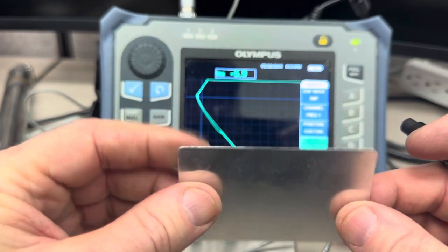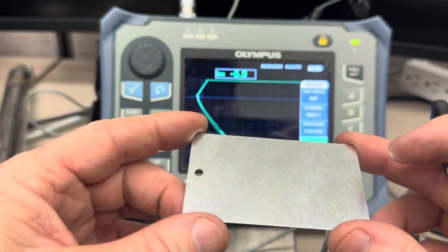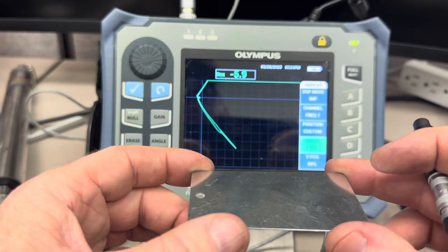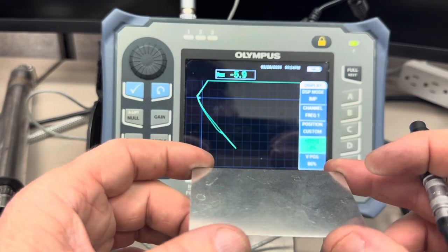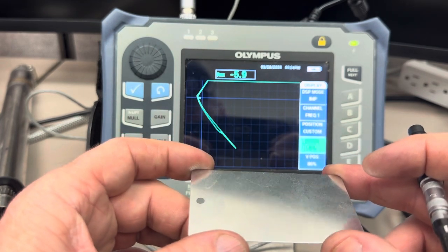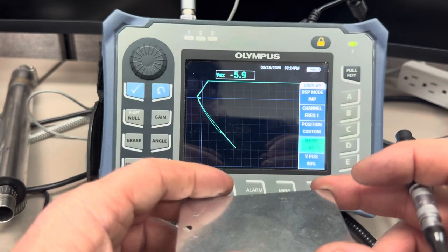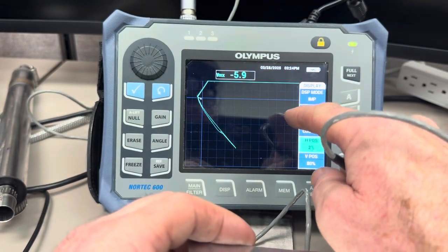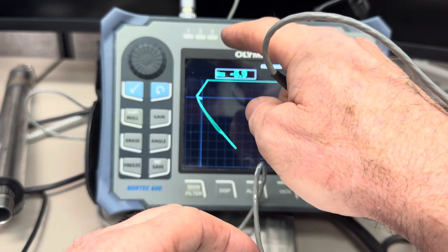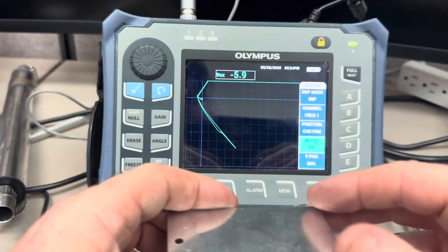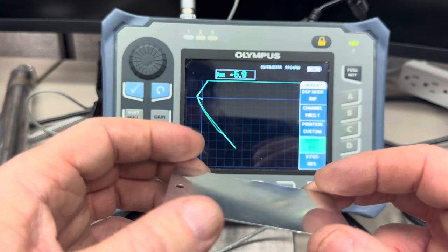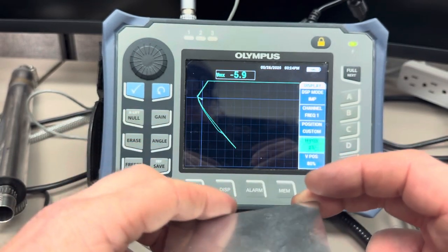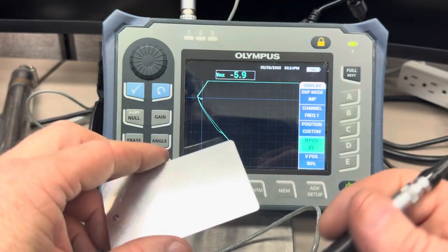Coating thickness always increases in a clockwise direction, whether you're putting higher conductive material on a lower conductive base or lower conductive material on a higher conductive base. The only difference is whether it's going clockwise to the right of the conductivity curve or to the left of the conductivity curve. And it's going to keep increasing until the material on the top gets so deep that it's infinitely thick for that test frequency. So let's demonstrate what I mean by that.